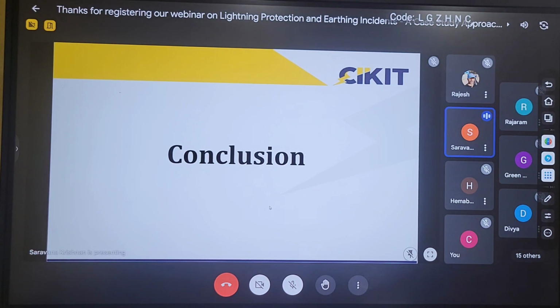Because of the increasing sensitivity of electronic devices, surge protection devices are nowadays becoming mandatory. If I want to provide protection to these electronic equipments, then the MCBs, fuses and voltage stabilizers which we are using won't be sufficient. So we have to go for separate devices called surge protection devices. These surges are called silent killers of electronic equipment. These low magnitude surges are very dangerous, and they may result in a reduction of the lifetime of the electronic equipment.